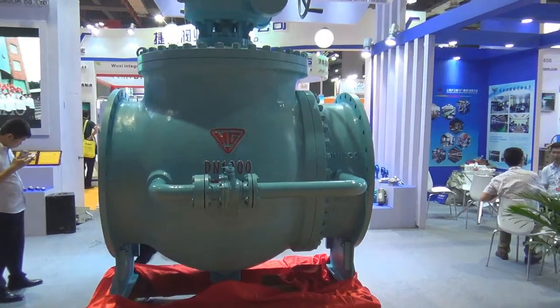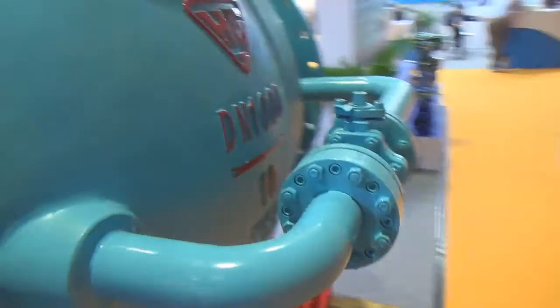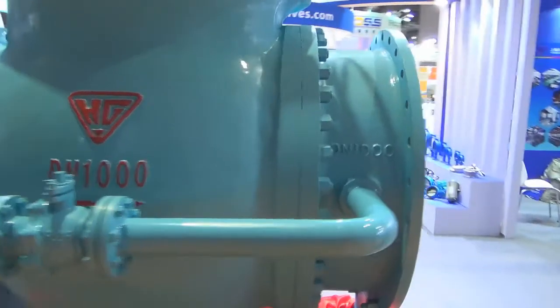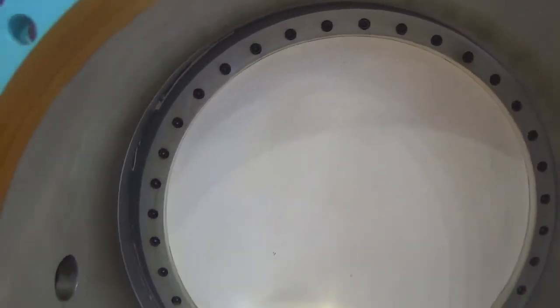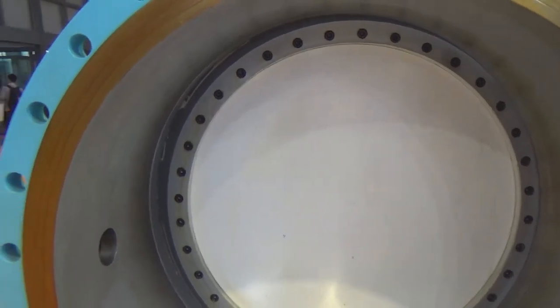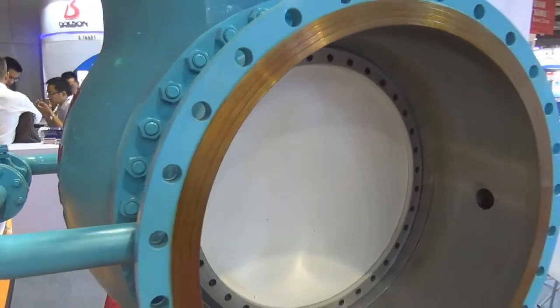Here we have a very big semi-eccentric ball valve. We use a half ball design for this kind of ball valve, and also the valve stem is not in the center of the valve body. So we call this kind of ball valve a semi-eccentric ball valve. When the valve opens, the ball sealing face will immediately leave the valve body seat sealing face. So the ball will not grab the valve seat. So when we open this kind of ball valve, it has no rubbing. The white color is just paint, not another kind of material.